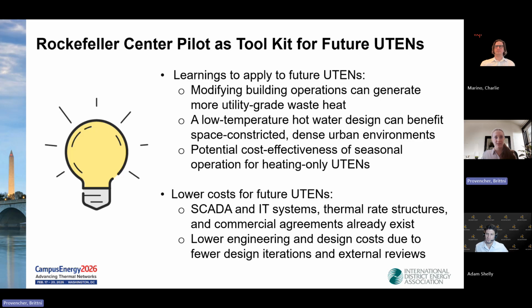Although hot water systems typically don't utilize ultra-low temperature designs, it made sense for the Rock Center UTEN due to space limitations to install a new machine in the central plant, which would produce higher temperature condenser water return. The ultra-low temperature operating range can also allow additional heat rejection from other nearby sources if the Rock Center UTEN is ever expanded in the future. This design opens up avenues for UTENs in areas that are otherwise constrained and couldn't implement a traditional hot water TEN.